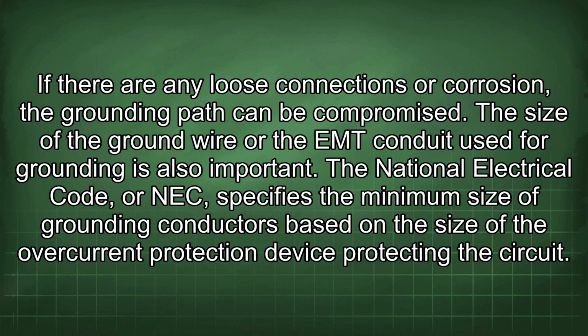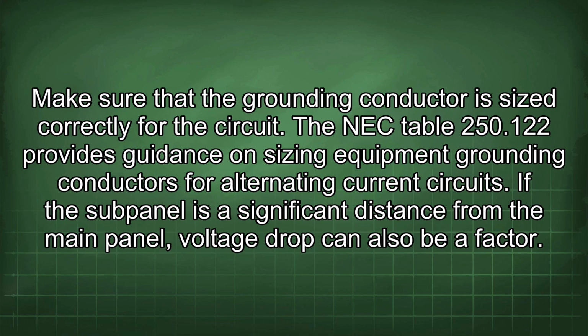The size of the ground wire or the EMT conduit used for grounding is also important. The National Electrical Code, or NEC, specifies the minimum size of grounding conductors based on the size of the overcurrent protection device protecting the circuit. Make sure that the grounding conductor is sized correctly for the circuit. The NEC Table 250.122 provides guidance on sizing equipment grounding conductors for alternating current circuits.